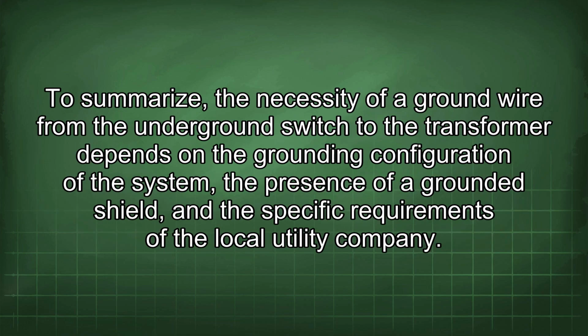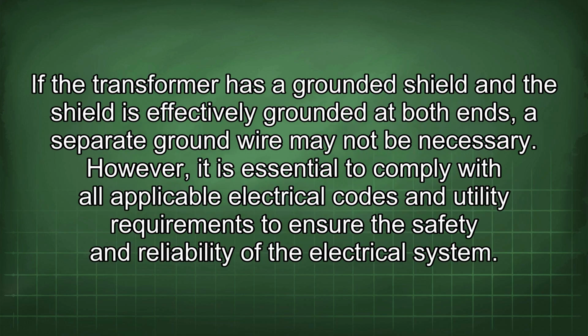To summarize, the necessity of a ground wire from the underground switch to the transformer depends on the grounding configuration of the system, the presence of a grounded shield, and the specific requirements of the local utility company. If the transformer has a grounded shield and the shield is effectively grounded at both ends, a separate ground wire may not be necessary. However, it is essential to comply with all applicable electrical codes and utility requirements to ensure the safety and reliability of the electrical system.